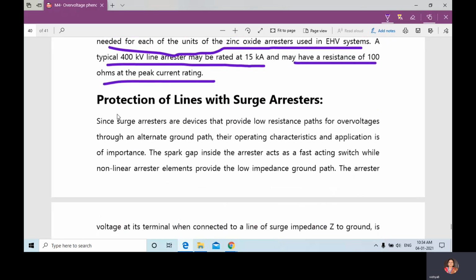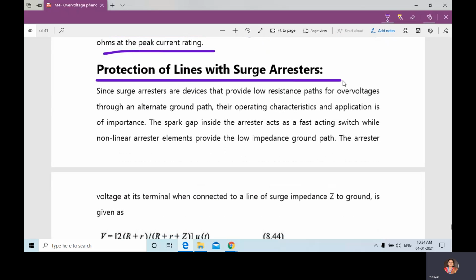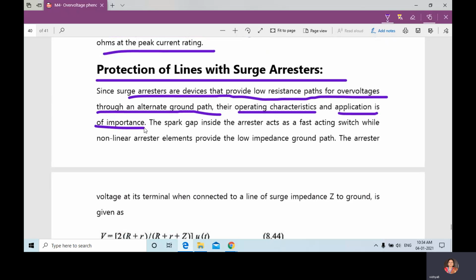Next is the protection of lines with the surge arrestor. Surge arrestors are devices that provide a low resistance path for overvoltage through an alternate ground path. Their operating characteristics and application are of more importance. The spark gap inside the arrestor acts as a fast-acting switch, while non-linear arrestor elements provide the low-impedance ground path.